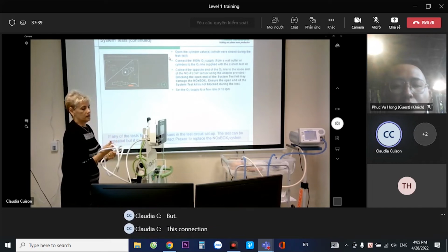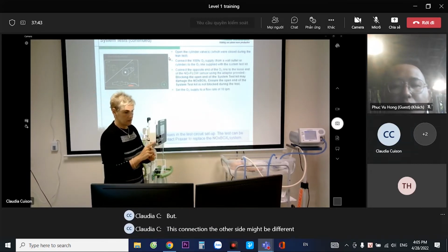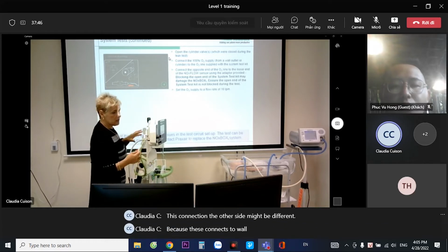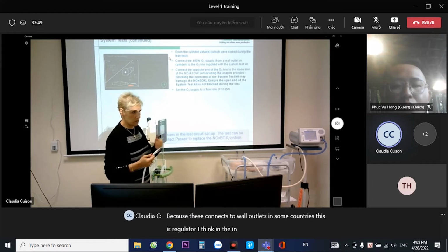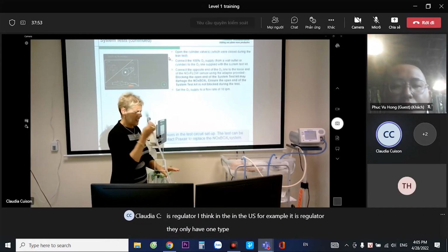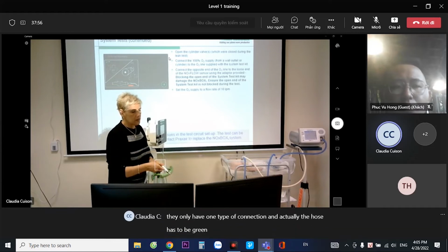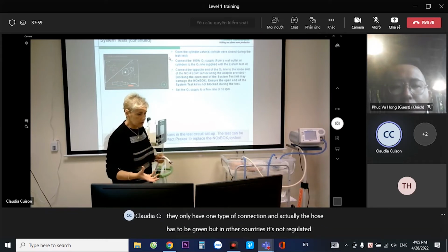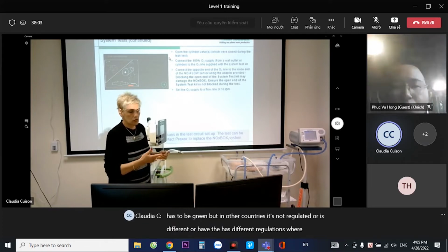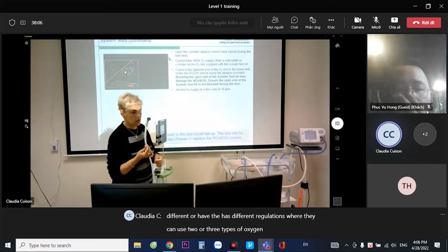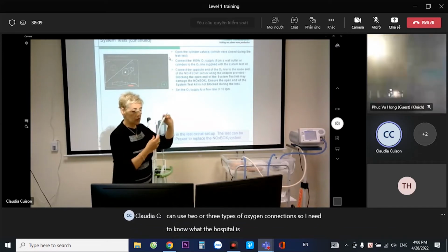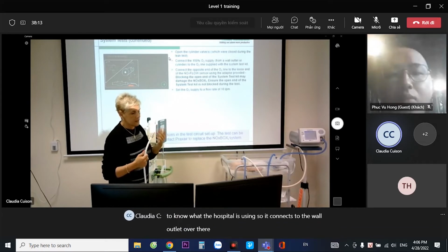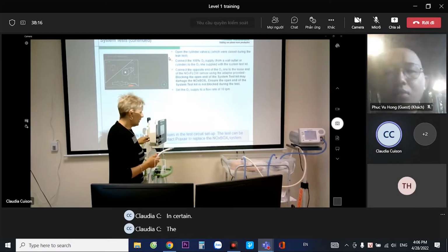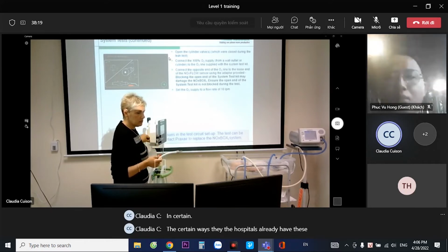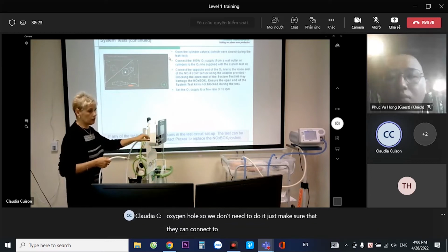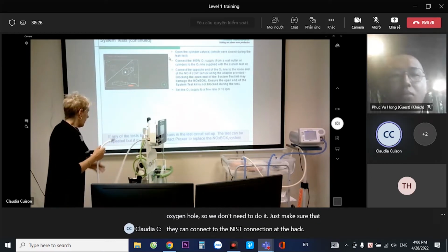And it's always the same. But the other side of this connection might be different because this connects to wall outlets. In some countries, this is regulated. I think in the US, for example, it is regulated. They only have one type of connection, and actually the hose has to be green. But in other countries, it's not regulated, or has different regulations where they can use 2 or 3 types of oxygen connections. So I need to know what the hospital is using so it connects to the wall outlet over there, okay? In certain cases, the hospitals already have this oxygen hose, so we don't need to do it. Just make sure that they can connect to the DISS connection at the back.